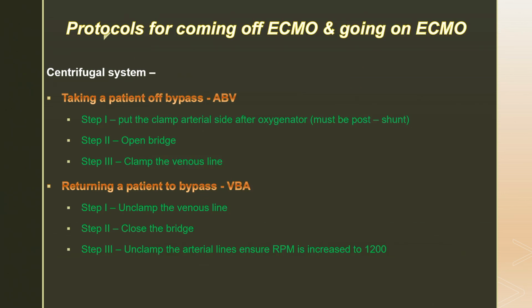So when you want to come off, put the clamp on the return line or arterial line, and when you go on ECMO, release the arterial line last. The reason, as I told you, is that it is a centrifugal pump, so it is a non-occlusive pump. If you don't put the clamp on the arterial line, there will be a reverse flow. So always remember that you have to put the clamp on the return line when you want to come off the centrifugal pump, and when you go on ECMO, you release the return line last. Those are the steps you need to follow.